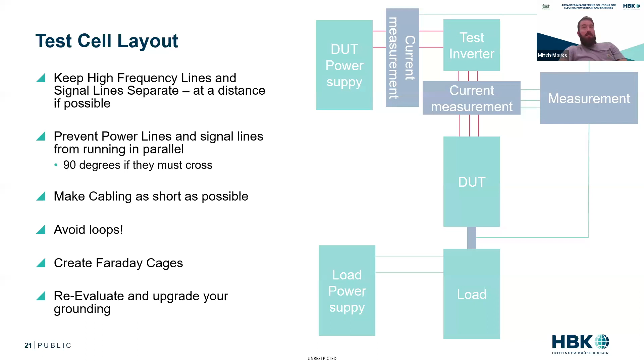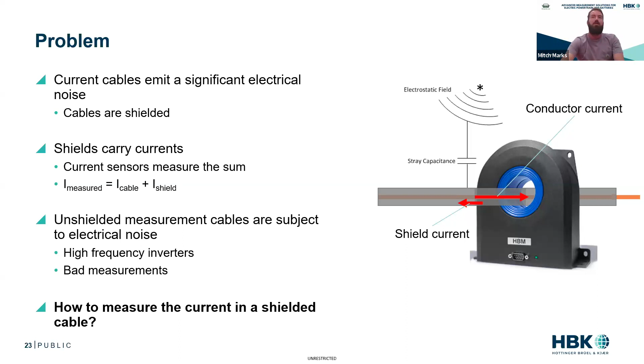Cabling and measuring current is quite challenging. These power cables emit a significant amount of noise. The shields on these cables are quite important to their operation, and the shields carry currents. Current sensors measure the sum of what's going through them, so my measured current equals my measurement cable current plus my shield current. If I have 100 amps going this direction and 1 amp in the shield, I'm going to measure 99 amps. I'll get a bad measurement. So we have to look at how do we measure this?